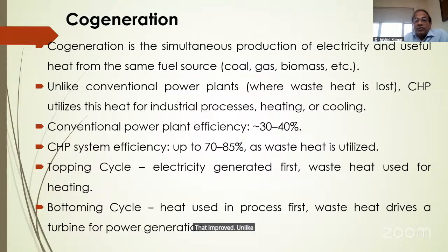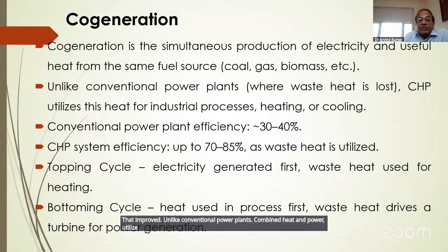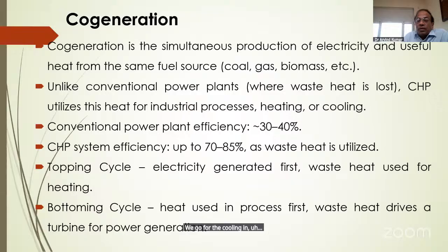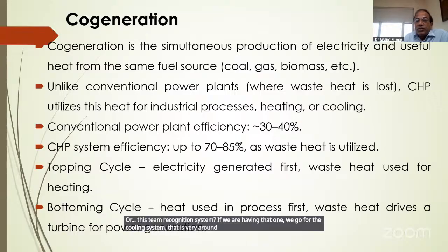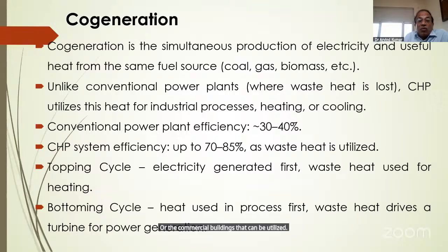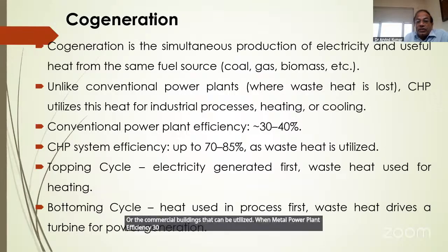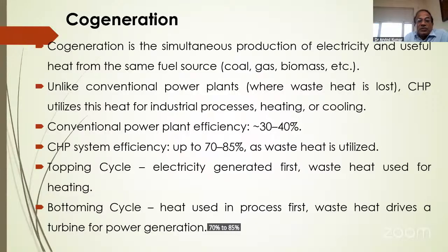Unlike conventional power plants, combined heat and power utilizes the heat for industrial processes, heating, or cooling. We can go for cooling in a vapor absorption refrigeration system or steam refrigeration system. That way, a lot of energy used in households or commercial buildings can be utilized. Conventional power plant efficiency is 30 to 40%, and with cogeneration we go to around 70 to 85%, as waste heat is utilized in the CHP system.